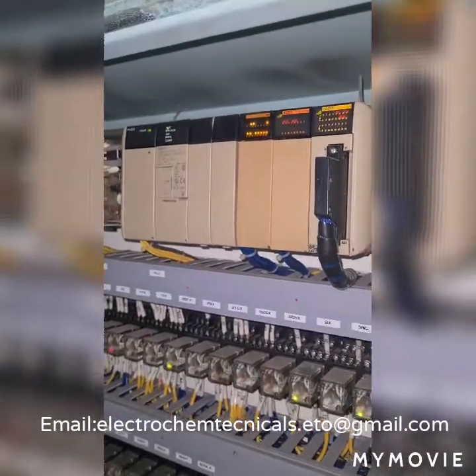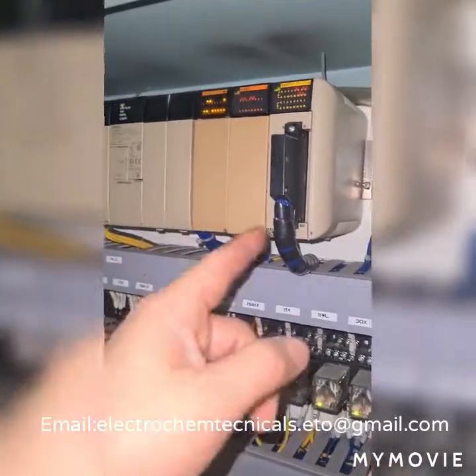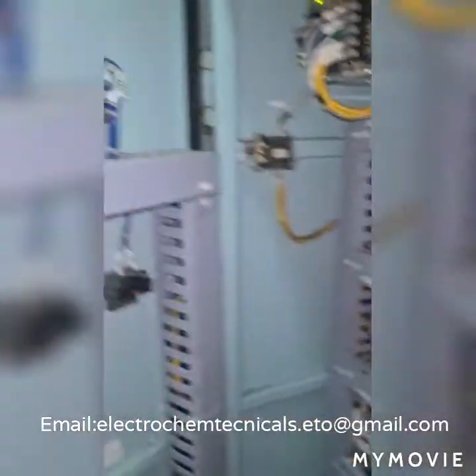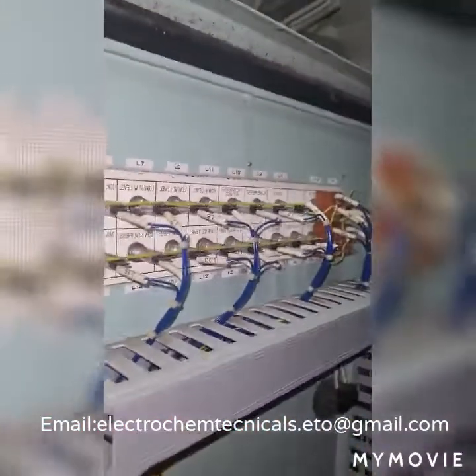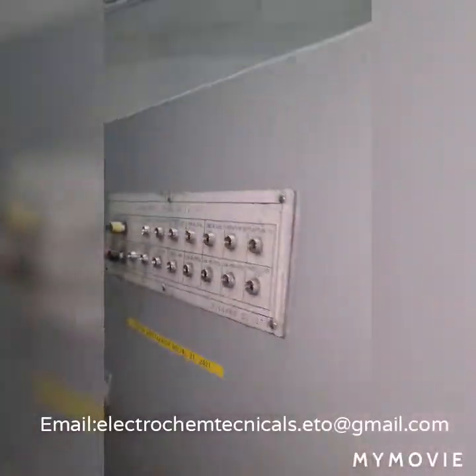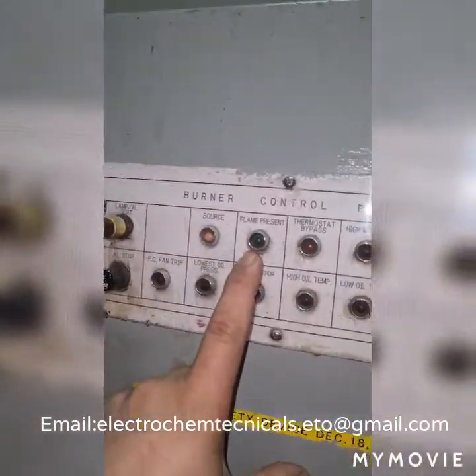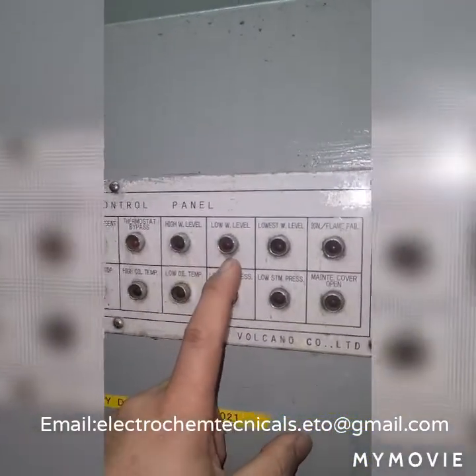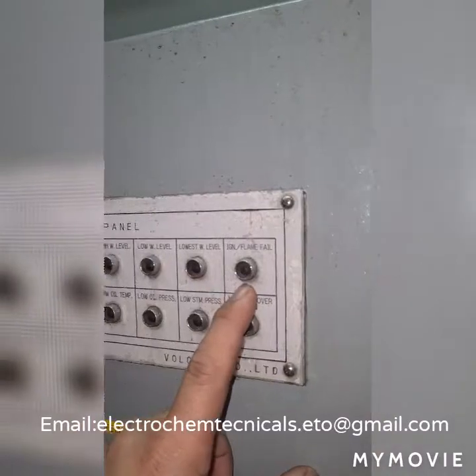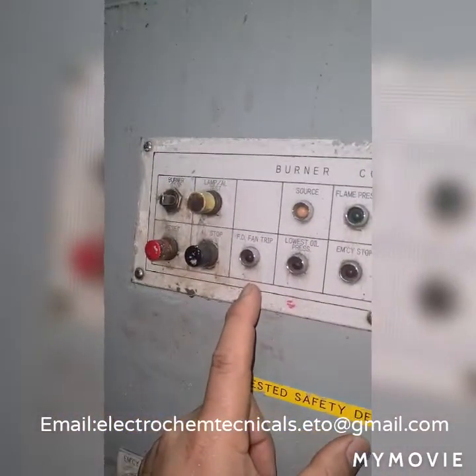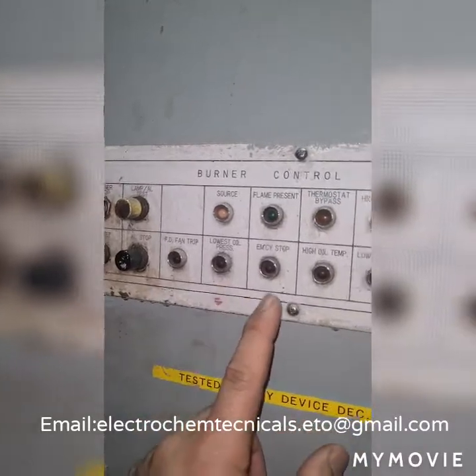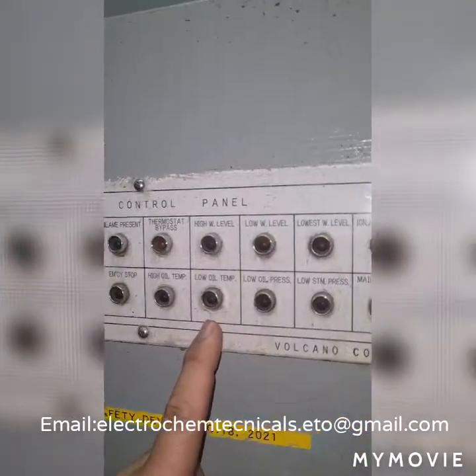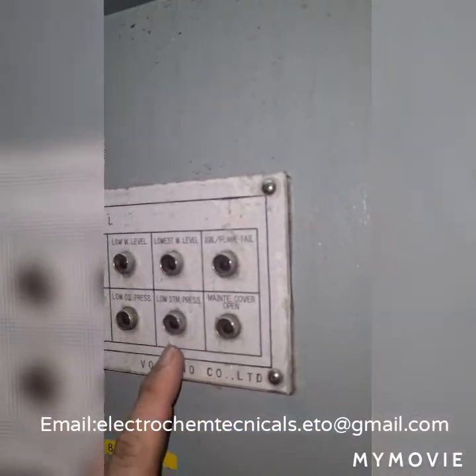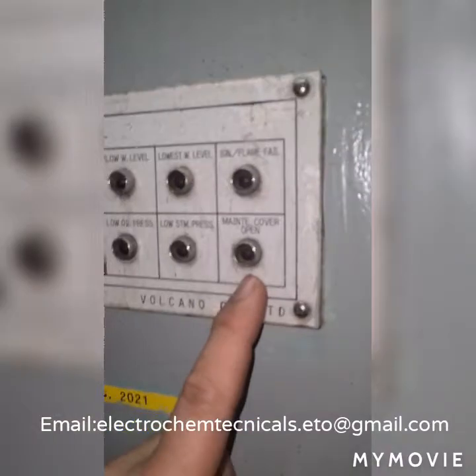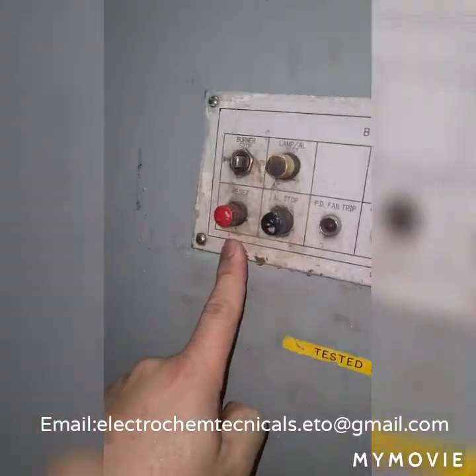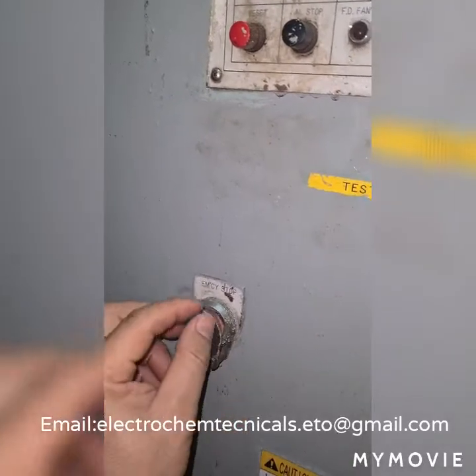As you will find, this is a sequencer and it has an output alarm going to the indicator lights. And those indicator lights are here: flame present, thermostat bypass, high water level, low water level, lowest water level, ignition flame fail, forced draft fan trip, lowest oil, emergency stop, high oil temperature, low oil temperature, low oil pressure, low steam pressure, maintenance cover open. This is the reset button, and this is an emergency stop button.